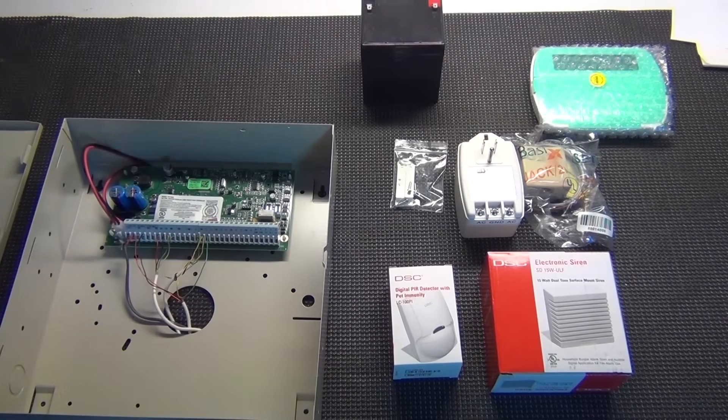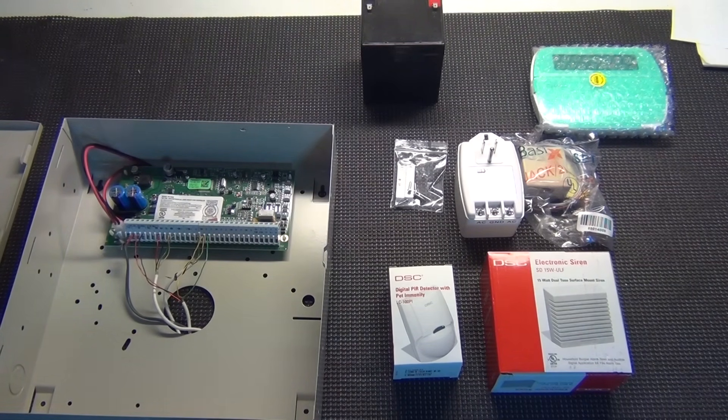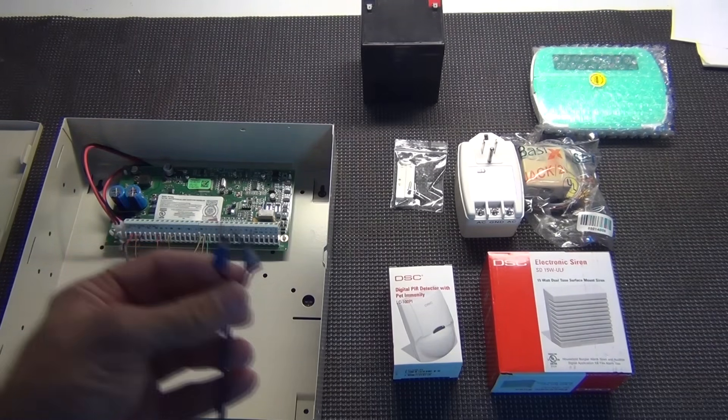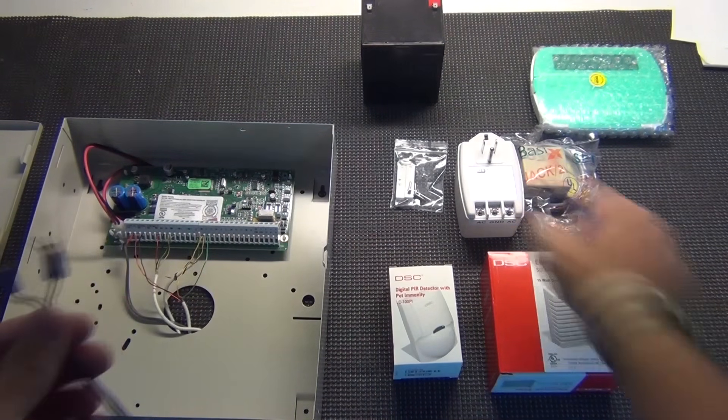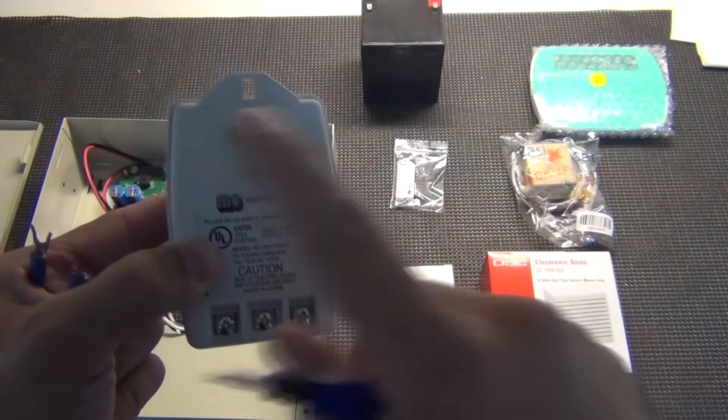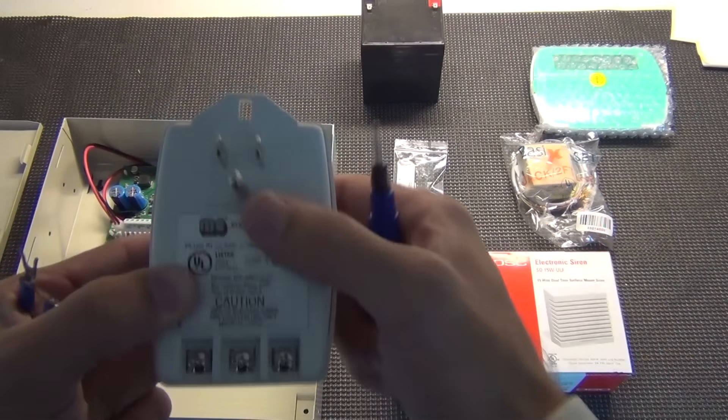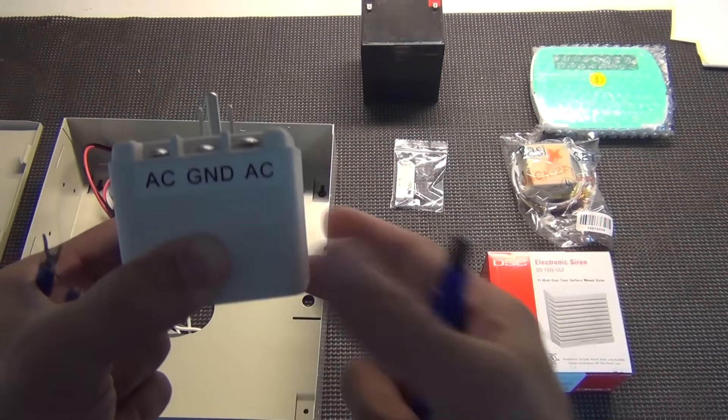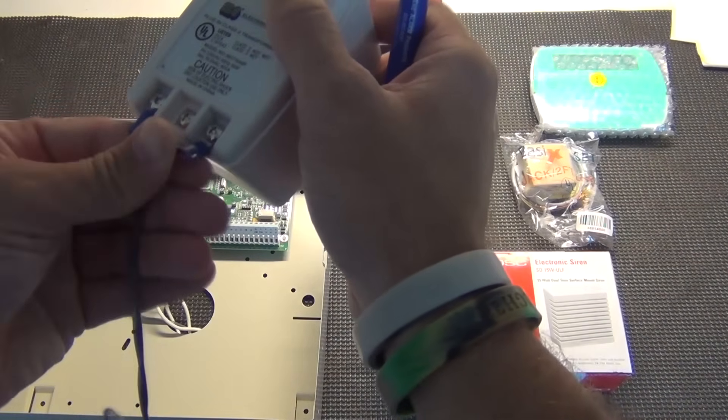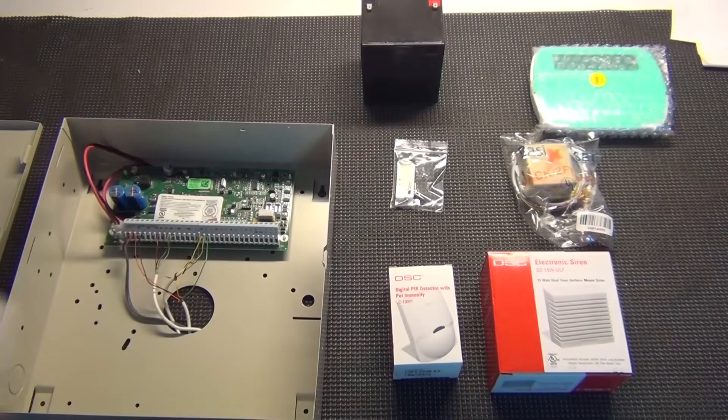Now on the other end is the power stuff. Here's the other end of my AC wire. I've got a couple of clips on there, which makes it a lot easier. And I've got my power transformer, 1640. Some of them look different. Some only have the two prongs. Some have the ground prong. In this case, I use the ground prong. You would just use AC and AC. You don't have to worry about the ground unless you're grounding it out. So we will use the AC and AC terminals. And as indicated before, it's non polarity. So it doesn't matter which wire goes where. I will not plug that in yet.